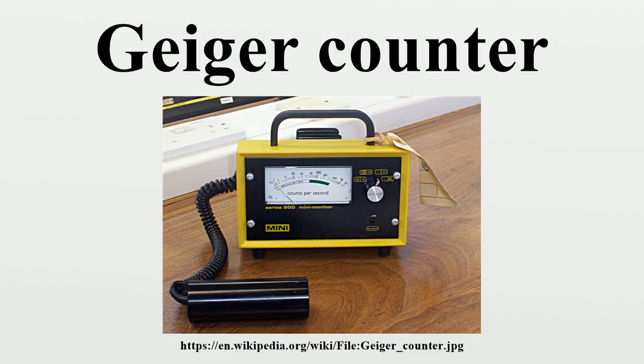Gamma and X-ray detection. Geiger counters are widely used to detect gamma radiation, and for this the windowless tube is used. However, efficiency is generally low due to the poor interaction of gamma rays compared with alpha and beta particles. For instance, a chrome steel GM tube is only about 1% efficient over a wide range of energies. The article on the Geiger Müller tube carries a more detailed account of the techniques used to detect photon radiation.